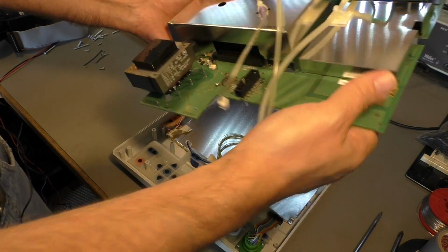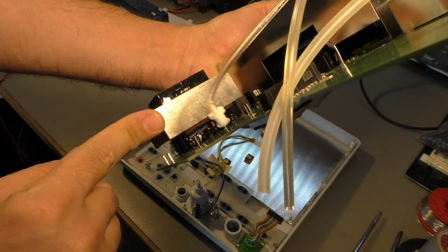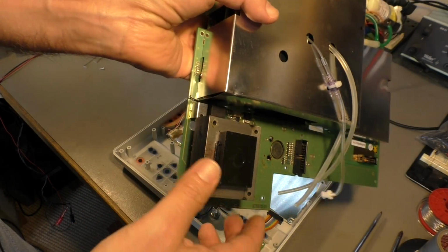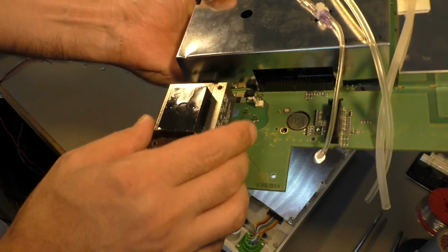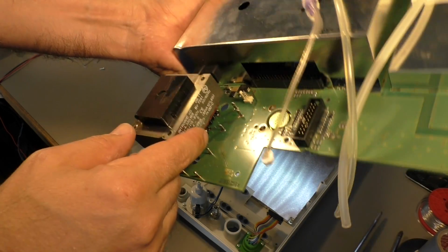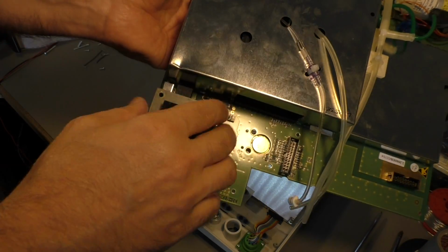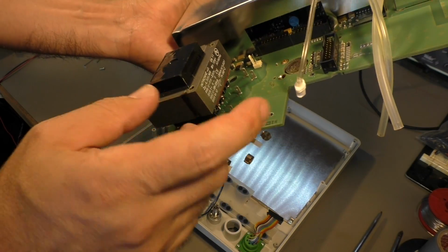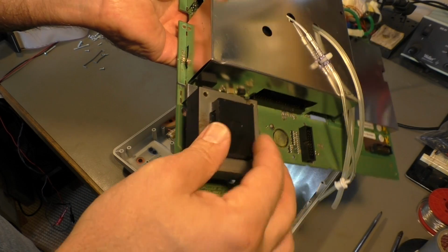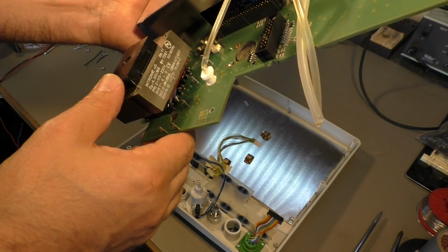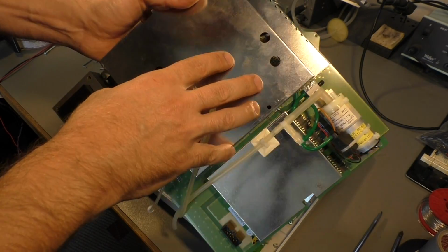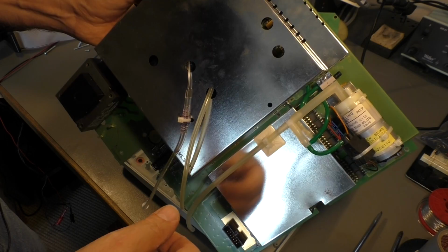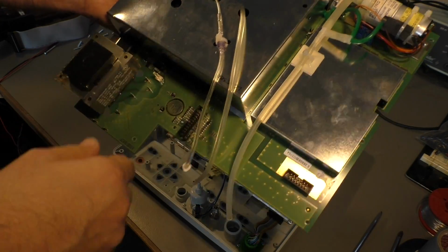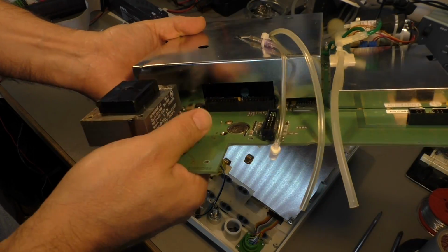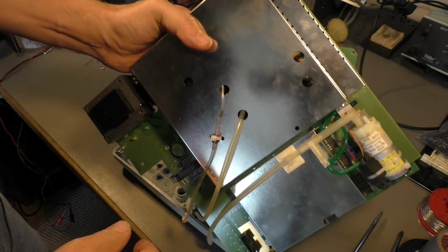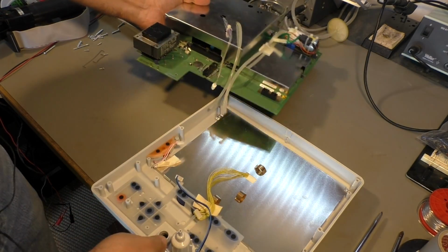I got the board out. You may have noticed there is just a normal transformer. That's the mains transformer. And many of these medical devices do have a traditional linear transformer because it's safer. They may have a switched power supply after the transformer, but for mains insulation they rely on big transformers. They're specially insulated, primary versus secondary, because on such a unit you're connecting a living human, and the last thing you want is that he gets shocked because your power supply is faulty or something like that. I think people that are attached to a machine like that have enough problems, so they don't need an electrical problem too.